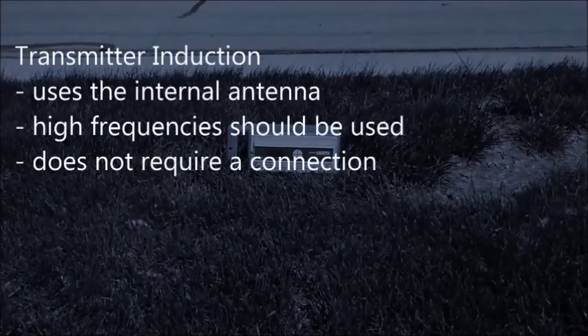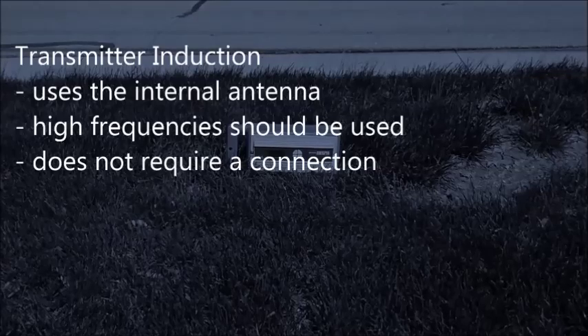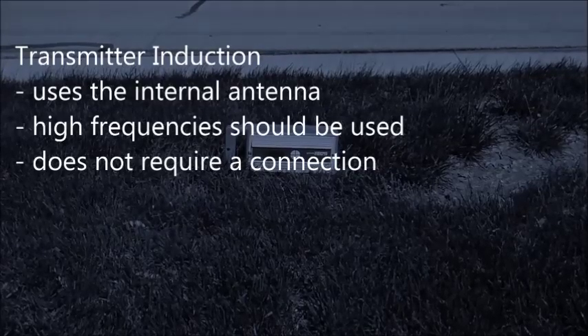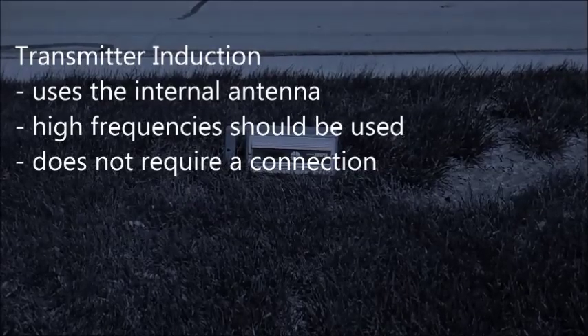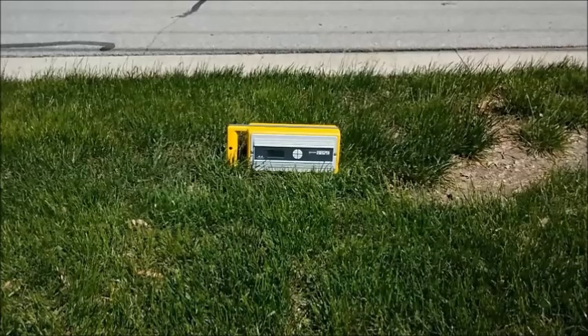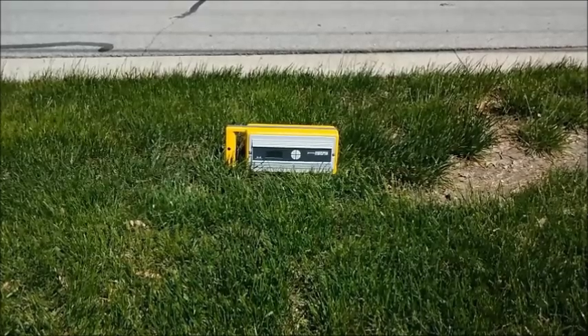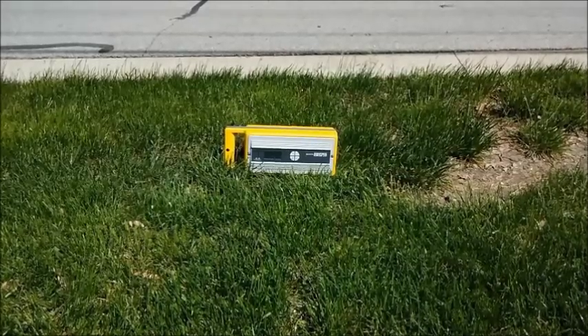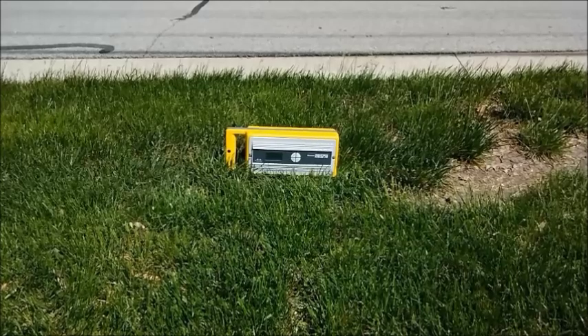Transmitter induction uses an internal antenna to broadcast the locate signal to a buried utility. High frequencies should be used for successful transmitter induction. To induce with the transmitter, place the unit on its side with the long axis in line with the buried utility. Turn the unit on the highest frequency.